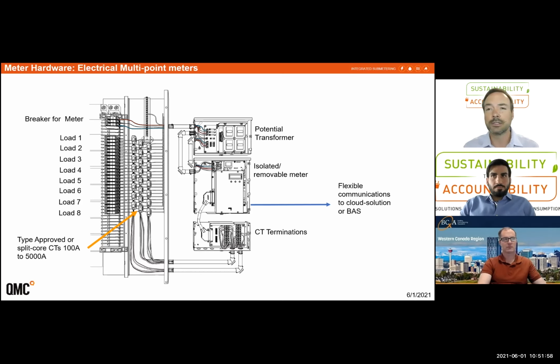So it's typically best to use solid core when possible, but split core you need to utilize often, especially in retrofit applications where you're dealing with bus bar or larger cables, or a load that can't be shut down for more than a few minutes, in which case you can go and put the split core CT on and then re-energize the power. There's not very many contractors anymore who want to do live CT installations with split core CTs, so you usually still need to shut down.